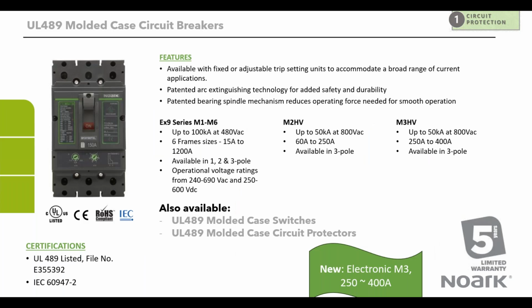So I'm moving on to the UL 489 molded case circuit breaker. We've got quite a number of series here, and I'm just going to touch on them briefly. So we've got our traditional EX9 series, M1 to M6, goes up to 1200 amps, 6 frame sizes. We've got operational voltage up to 690 volts, and for DC rating, we can do 600 volts, but it has to be wired in series.